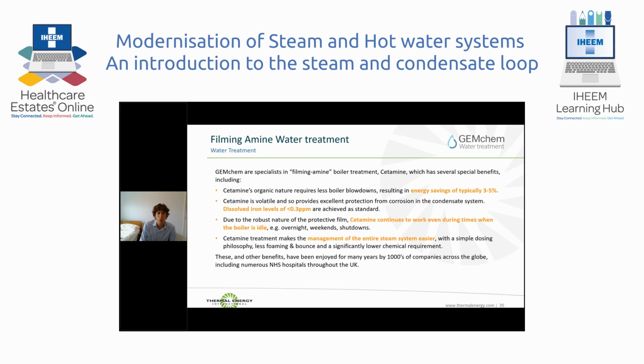These filming amine water treatments have several benefits. First of all, it's a pure liquid, so it doesn't add to the TDS at all, reducing the amount of boiler blowdown. Energy savings can be realised between 3 and 5%, depending on the existing blowdown level. The actual cetamine itself is volatile. That means that it evaporates out of the boiler with the steam, travels around your steam system, providing protection for the steam and condensate system.